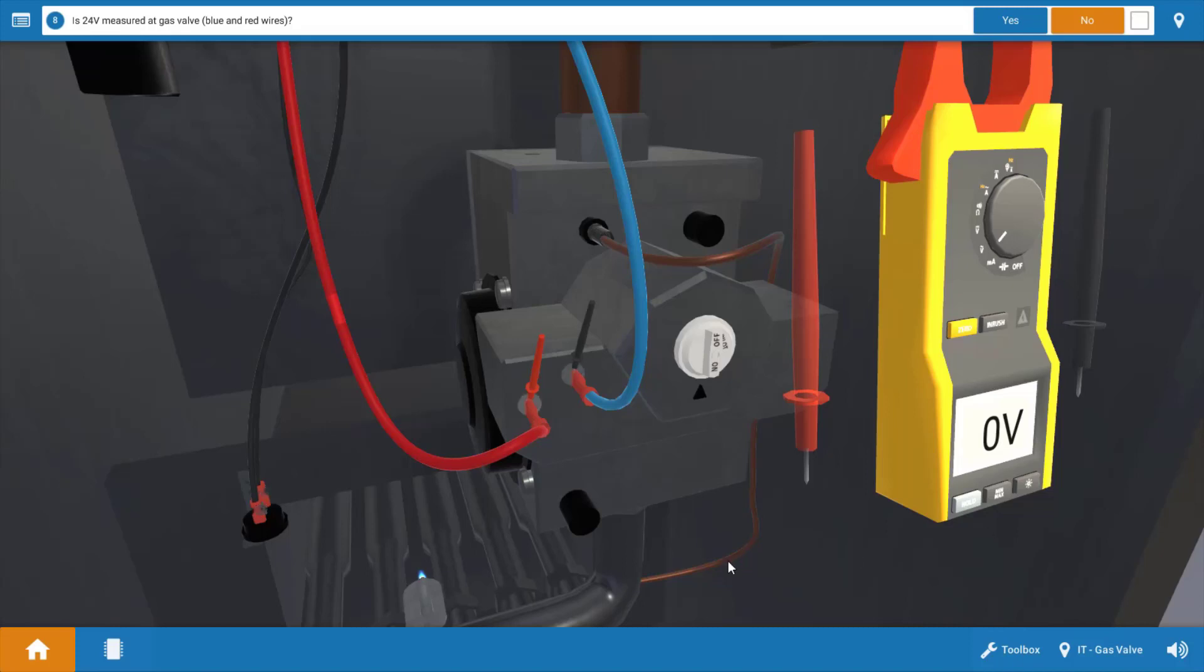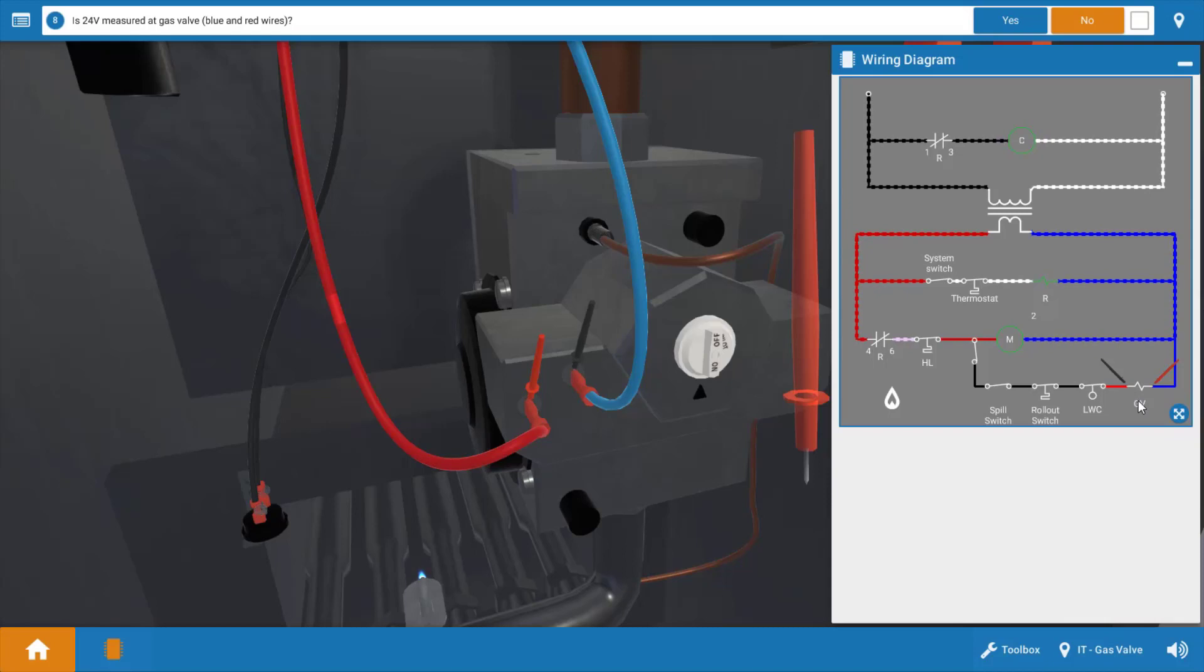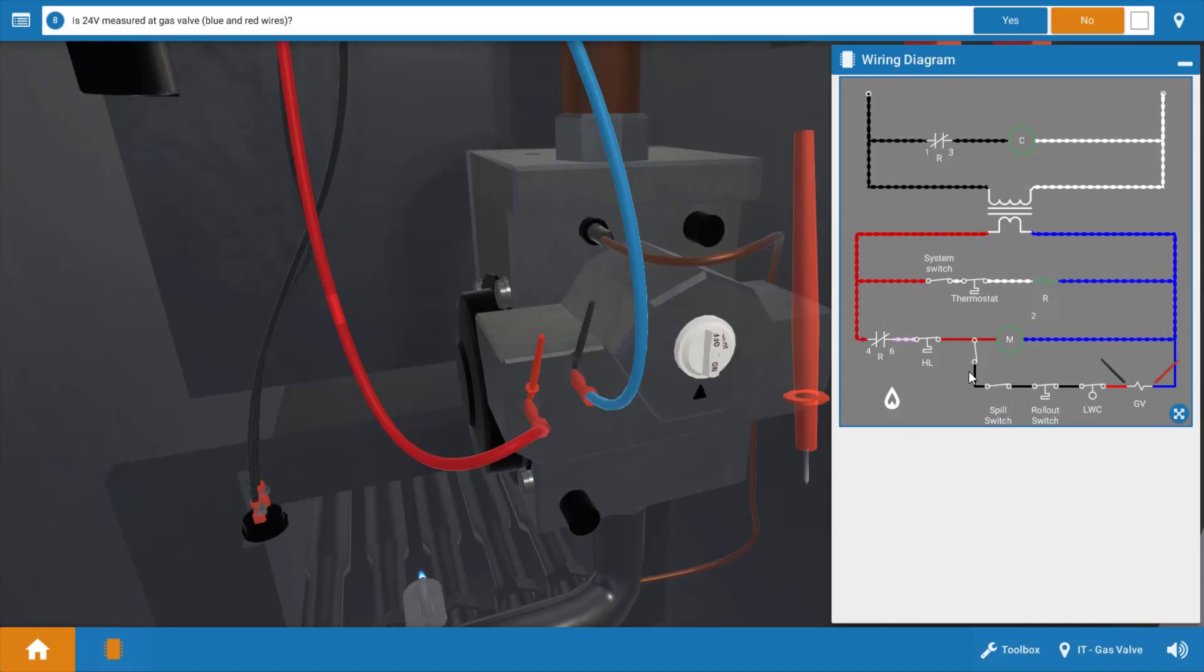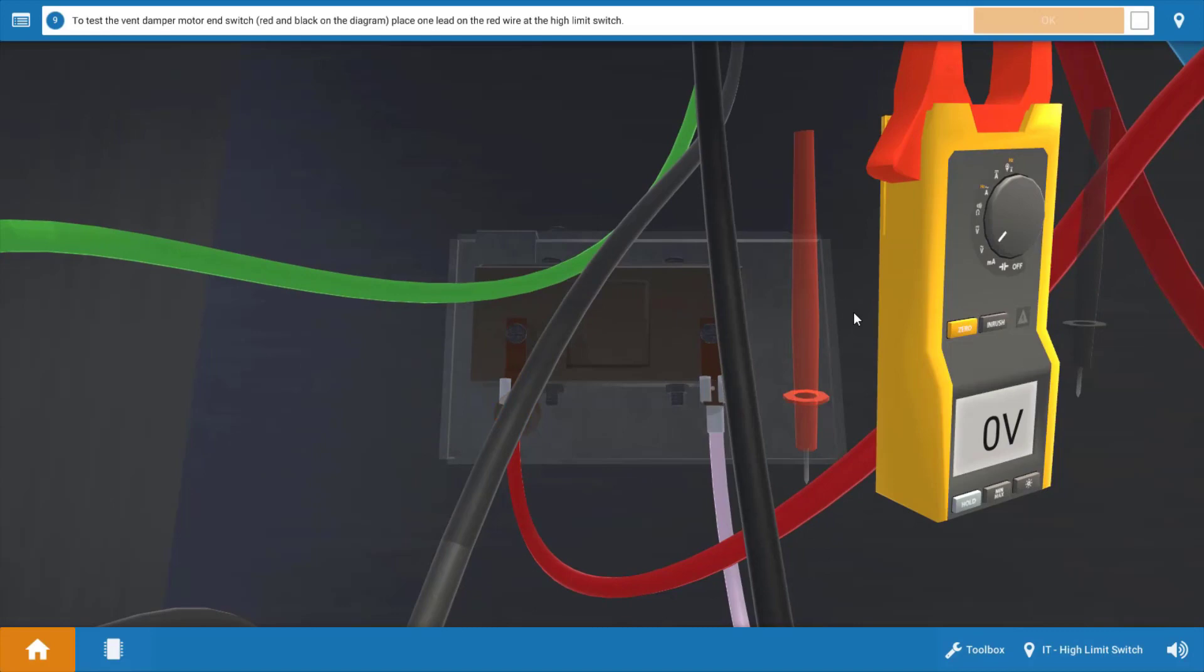Before I proceed any further I'm going to take out the wiring diagram and discuss the potential possible causes of this malfunction. We can see our meter leads placed here on the wiring diagram at the gas valve and we have zero volts here. What this means is that one of these four switches in this line leading to the gas valve are open. It could be the low water cutoff, the rollout switch, the spill switch, or possibly the end switch or proving switch in the vent damper motor. Although the vent damper motor is functioning we don't know that the end switch is actually closed.